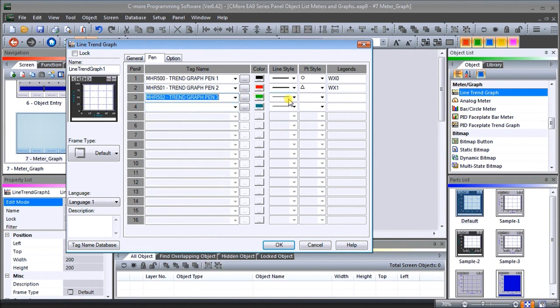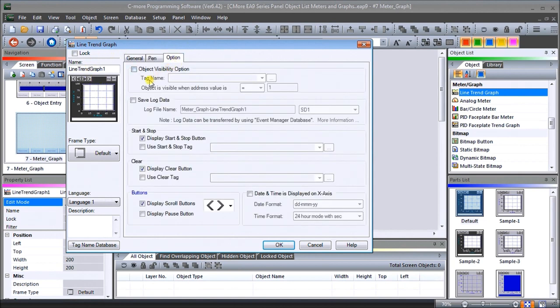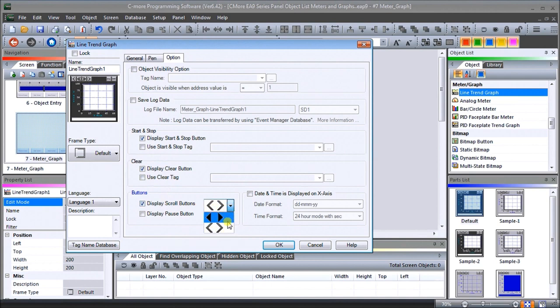The third pen we'll leave as light green — we'll use a darker color and set a square for the point style, with the legend as WX2. We'll put in three pen marks to show on our trend line. Under options, we have our visibility, our start and stop display which we'll leave on, and a clear button. We can also use a clear tag to control this from the PLC program. We'll display scroll buttons and can also add time and date to each point. Everything else left at default, we'll hit OK.